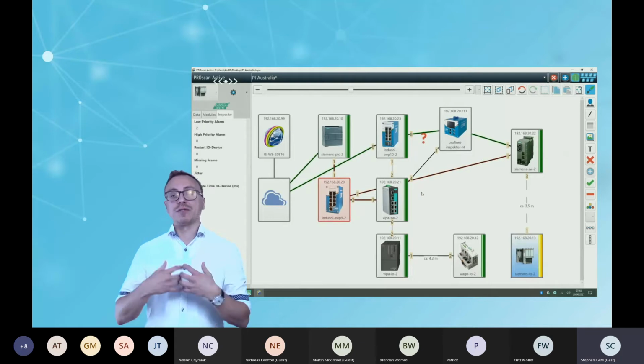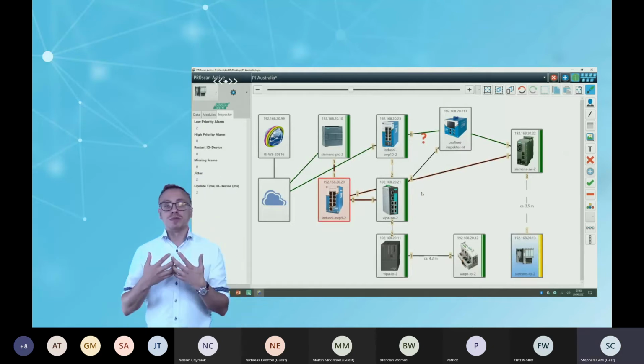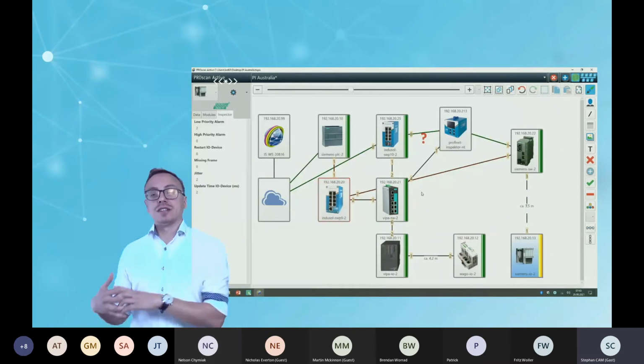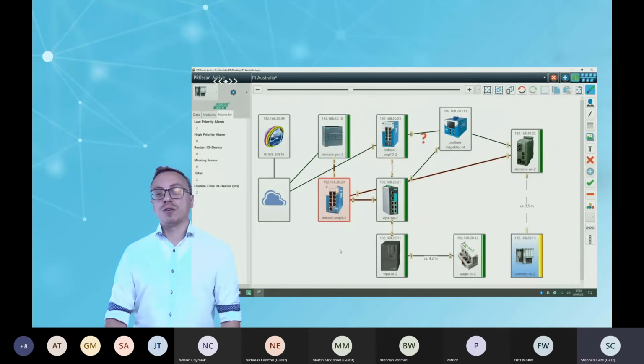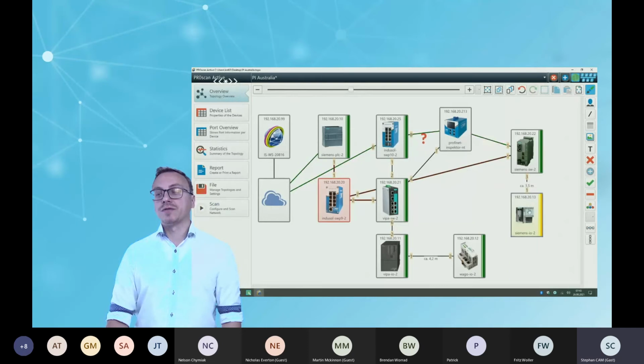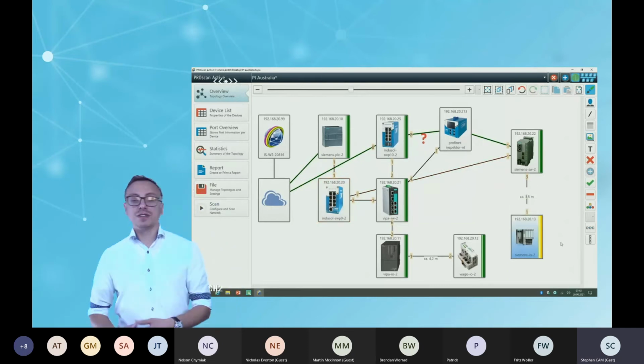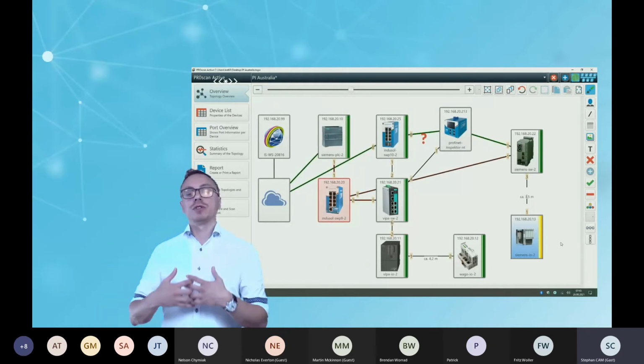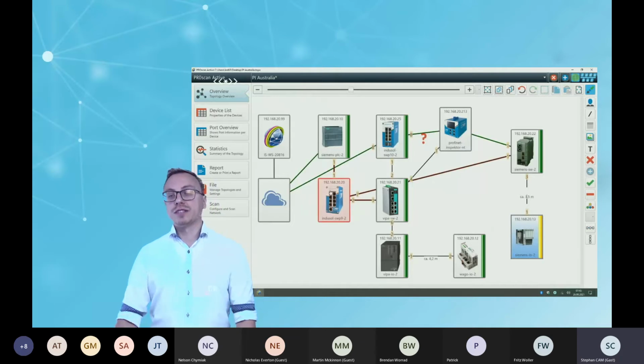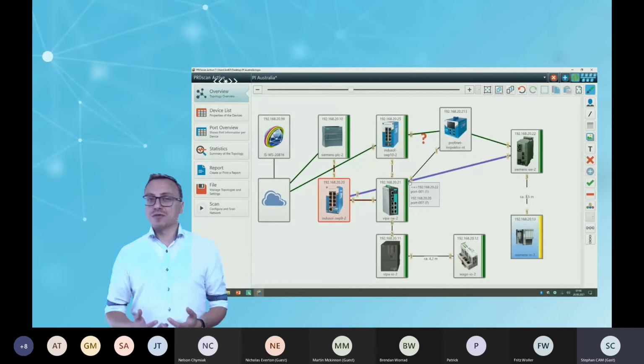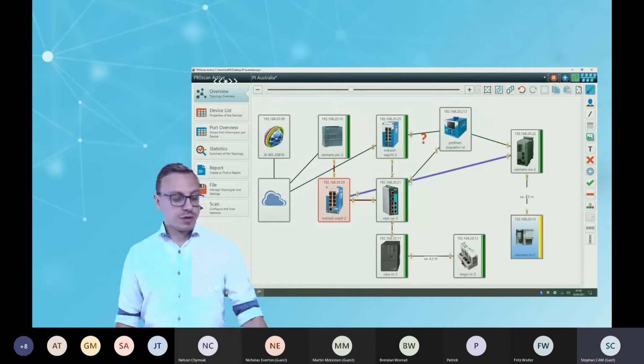For example, my first scan was made by the cable installation guys, and the last scan is made by the maintenance guys, and now the maintenance guy says, oh yeah, something has happened. Some people changed the switch, so we changed the wiring, and we maybe have some issues on this device. And as I said, the nice thing, if you have a big plant and now you have net load issues, or now you have discarding frames, you will see in this topology very easily, okay, till this device everything is fine, and after that it starts with discarding frames, with telegram gaps, and now you know, okay, all these three devices have some problems with frame gaps. So that means we have an issue in this part of the plant. And you get this information before you get a stop of your plant if you do some measurements on your own.